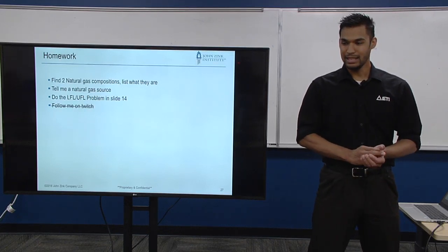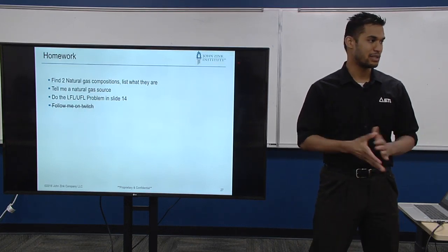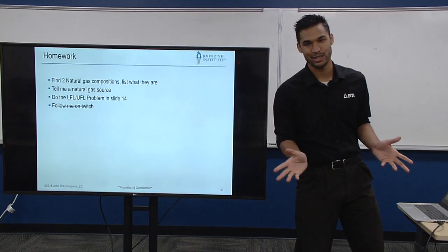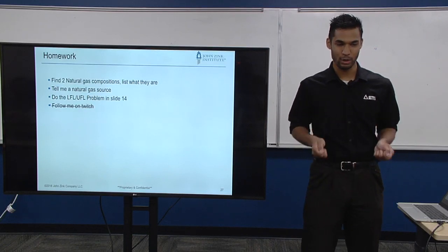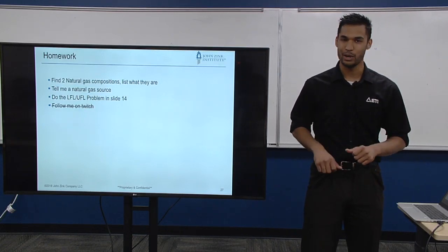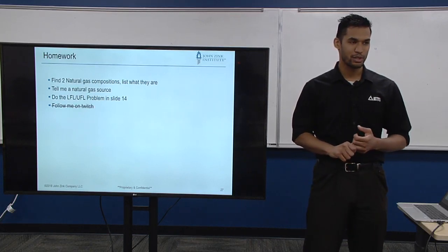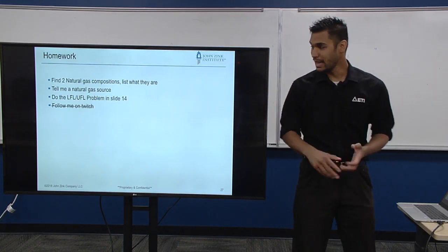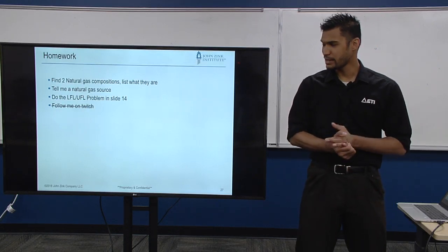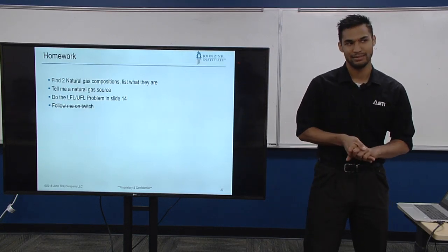And I'm like, yeah, you can't just flow it. You have to redesign the tips. So we did a lot of testing. We have a test furnace at John Zink where we can design equipment, put it in the box, and fire it up and let it go. It was a really long, intensive project, but it was fun too. So yeah, not all natural gas is the same. Tell me a natural gas source. How do we get natural gas?